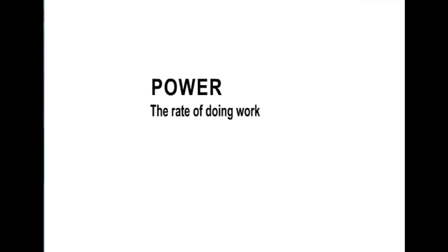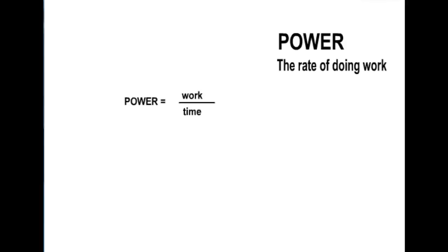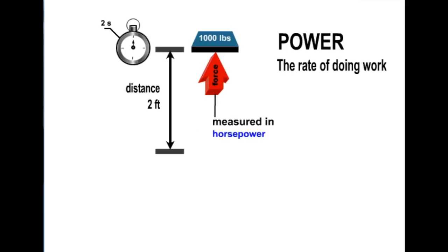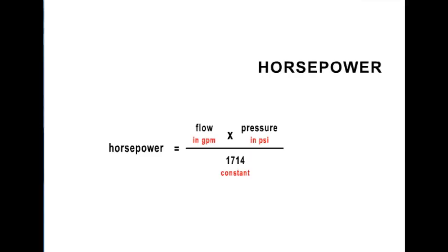Power may be defined as the rate of doing work, or work over time in seconds. If we lift 1,000 pounds 2 feet in 2 seconds, we have accomplished 1,000 units of power, or 1,000 times 2 divided by 2 seconds. To give us relative meaning for measuring power, we must convert this to horsepower, which is a unit of measuring energy. Mathematically, hydraulic horsepower is expressed as follows. Horsepower equals flow in gallons per minute times pressure in pounds per square inch divided by 1,714, a constant.